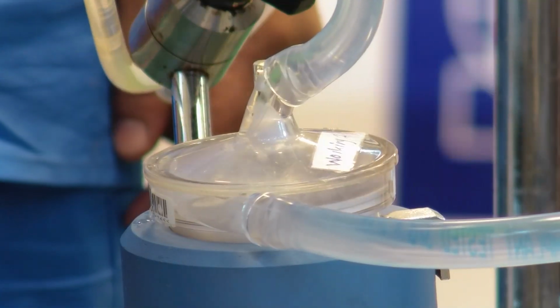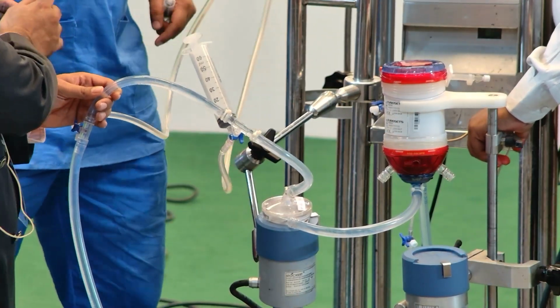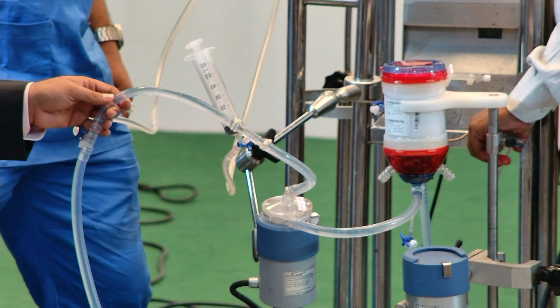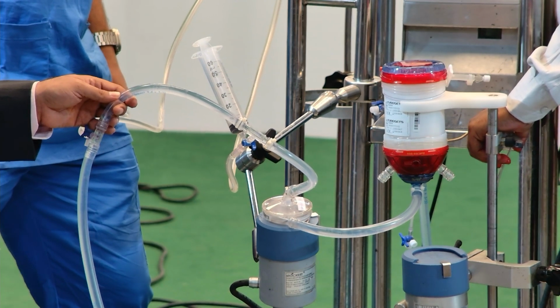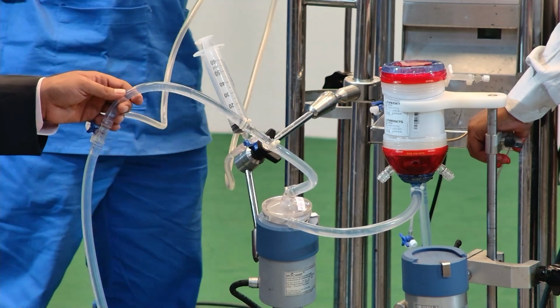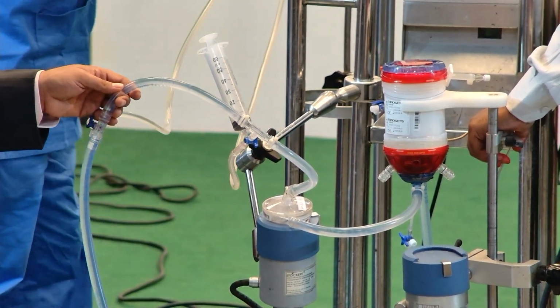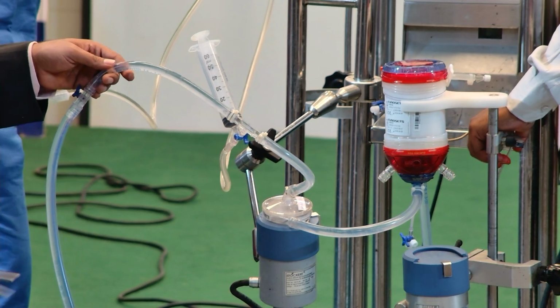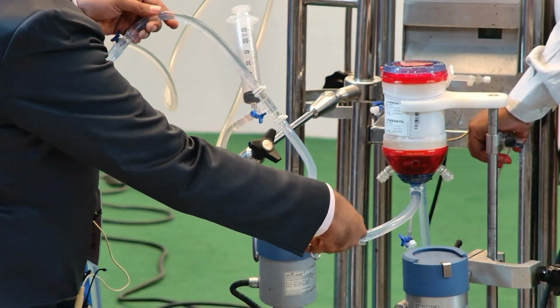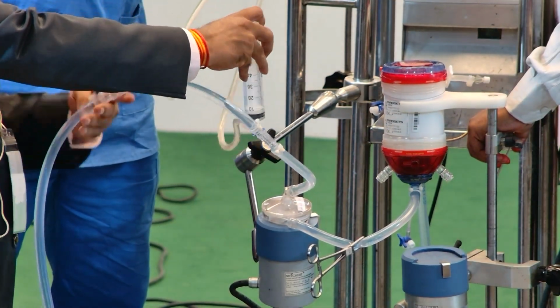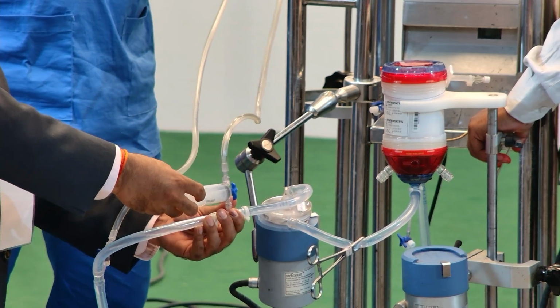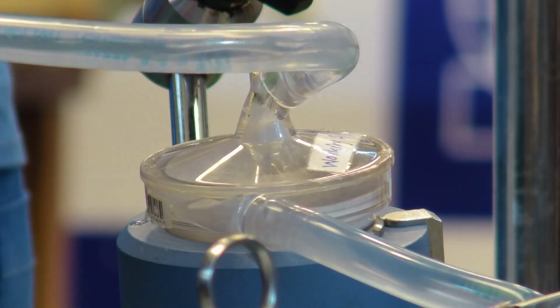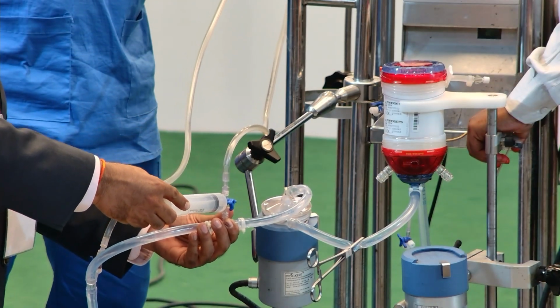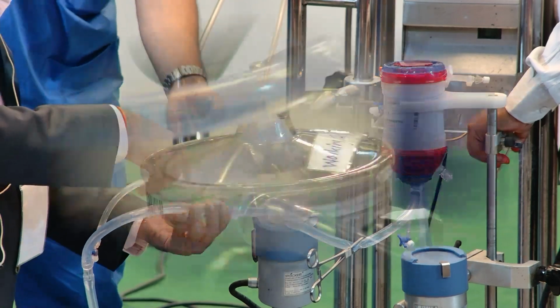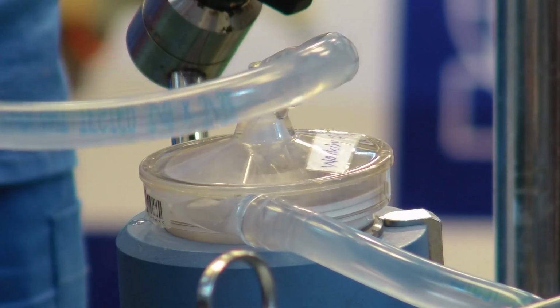Okay, then depending on the patient's stability, if the patient is stable and can be taken off ECMO for say 10 seconds, 20 seconds, 30 seconds, you can completely stop the flow. So when you are stopping the flow, put the clamp in the return line. When I say return line, it means anything after the pump. See, when I put the clamp here, the air comes up, isn't it? So I take the air like this and I aspirate it. Now if the patient is stable, I can aspirate the entire air at one go.